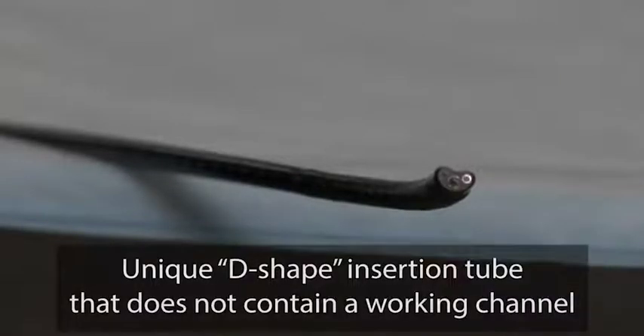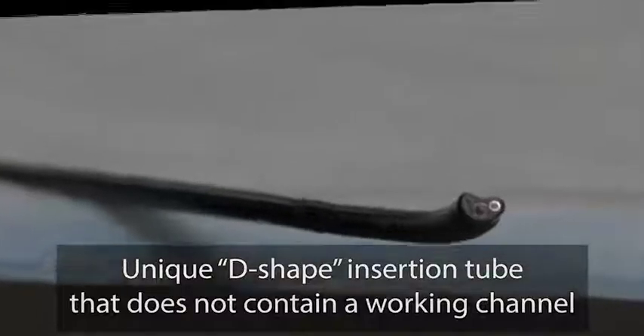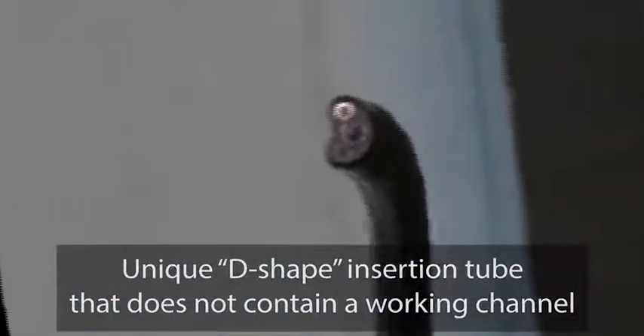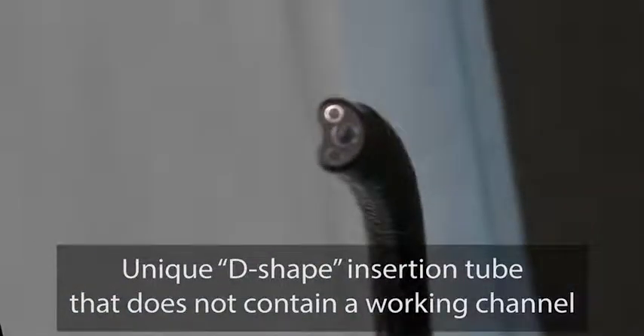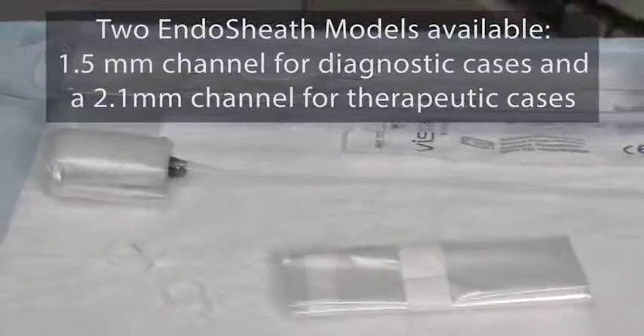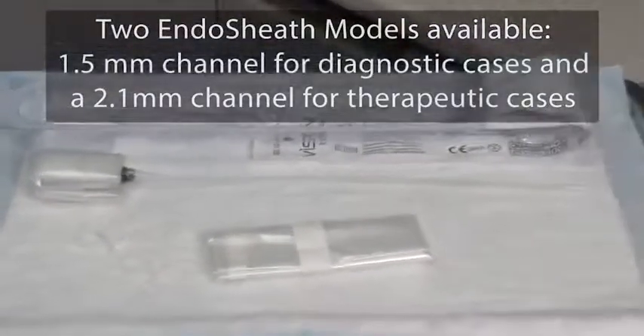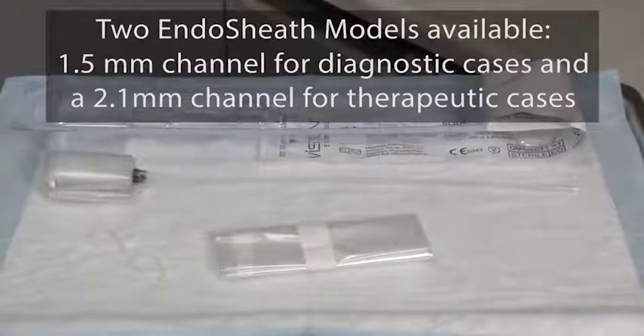The CST-4000 Flexible Cystoscope contains image and illumination features like other cystoscopes. But unlike conventional scopes, the CST-4000 has a unique D-shape insertion tube that does not contain a working channel. Instead, the CST-4000 utilizes the patented EndoSheath technology, a sterile, disposable sheath that fits snugly on the scope, providing a barrier between the endoscope and the patient.